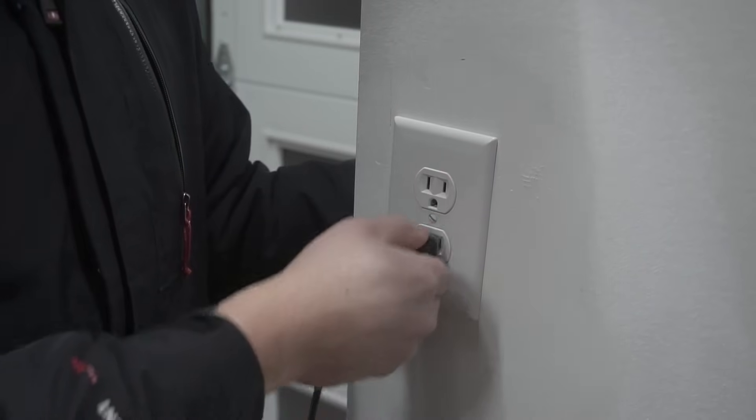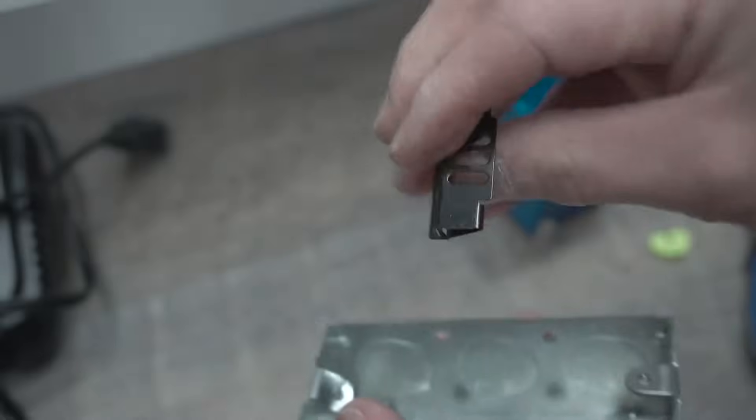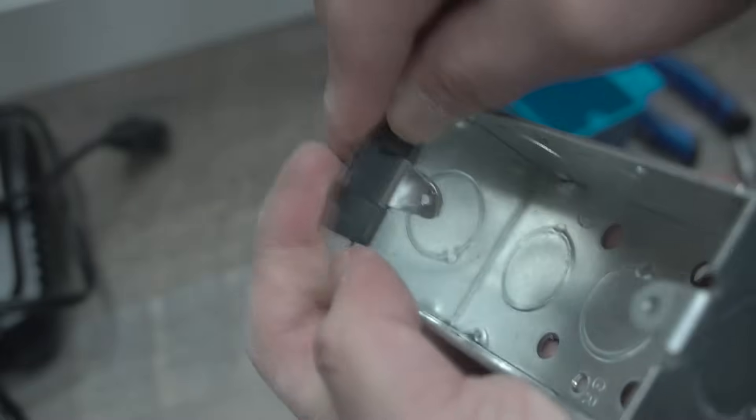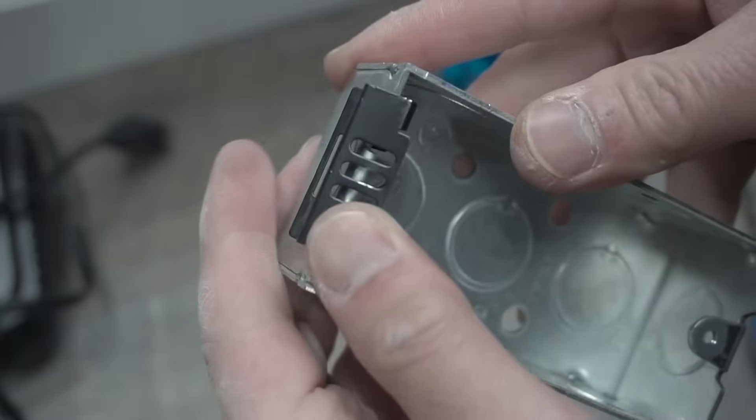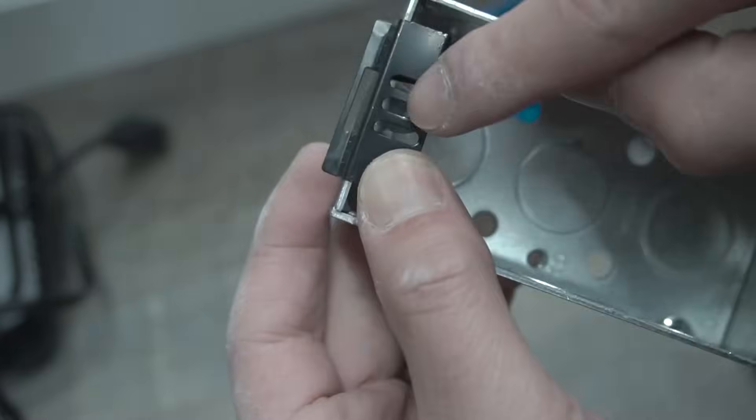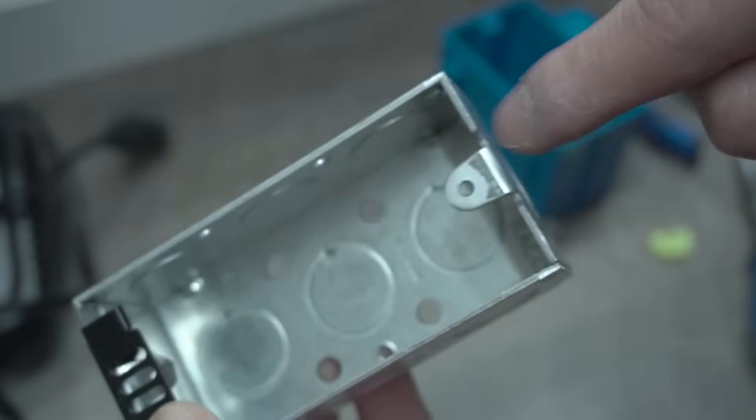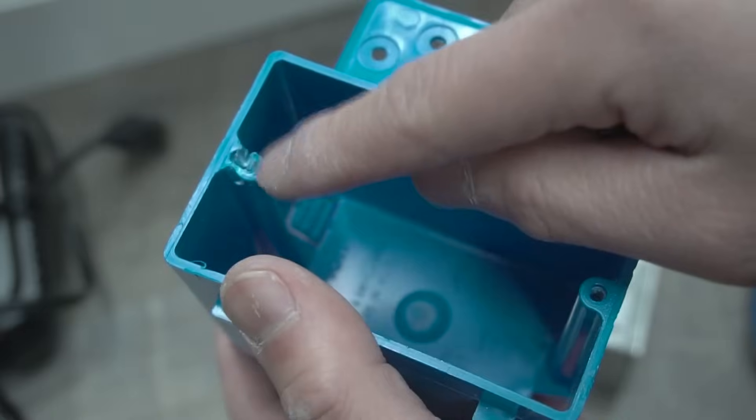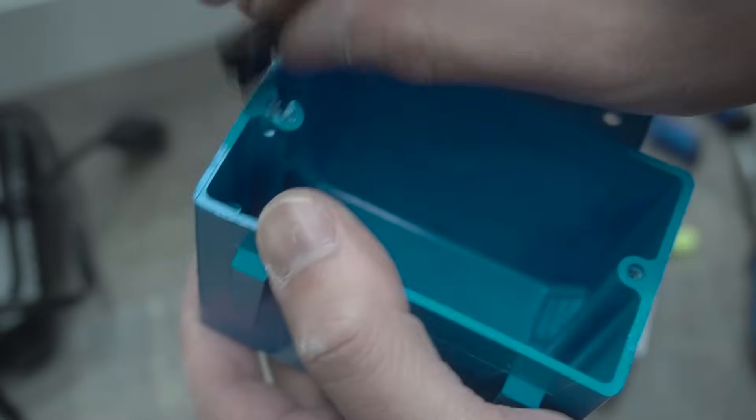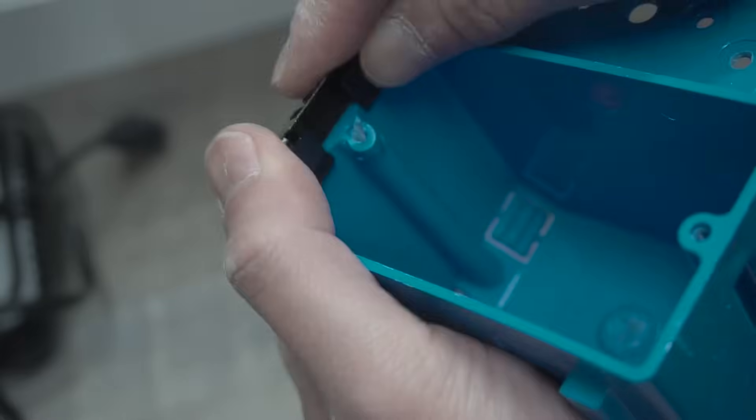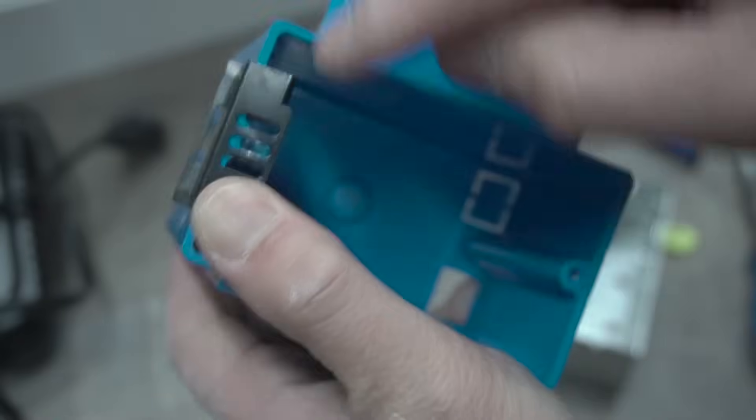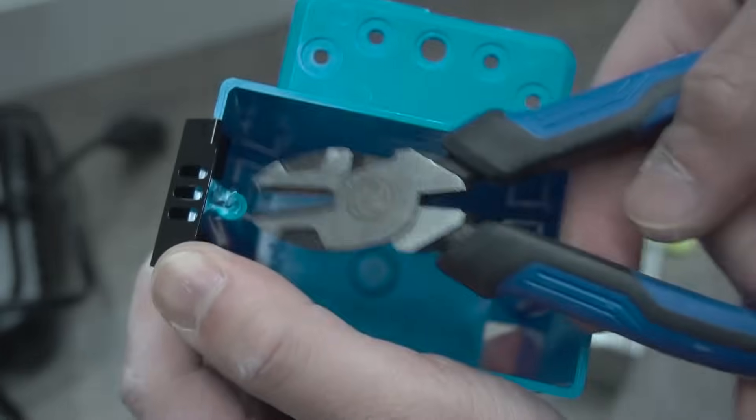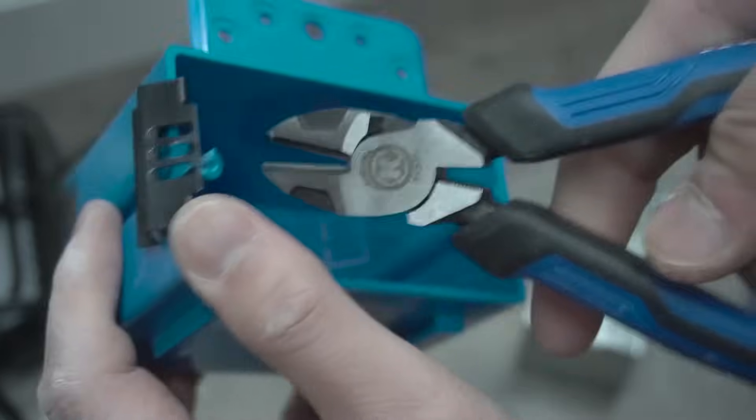This is actually the fastest and easiest solution that's why I made it tip and trick number one. So what's great about these clips is they work for the metal electrical boxes as well. You can just clip it on there. You see how it just places right over the damaged area and it replaces this access for that hole and now you have a nice place for your screws which will align with that. And this is actually great for this type of scenario as well. I've seen a lot of these cases right here where this is damaged and you can also use this clip over that as well. Most of the time, this clip will work on most boxes just like that. See how it replaces it.